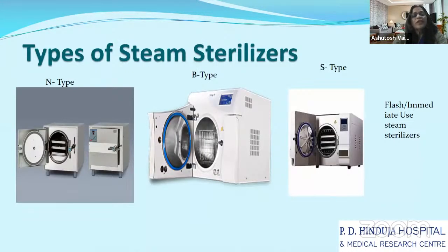So looking into types of sterilizers, they could be categorized into two main types: gravity sterilizers and vacuum sterilizers. Gravity sterilizers have no vacuum; the air is removed through pressure. So they are called N type sterilizers. And there is the S type of sterilizer, which uses a single vacuum in the process.